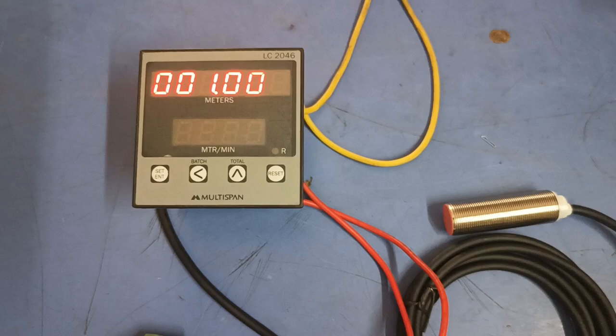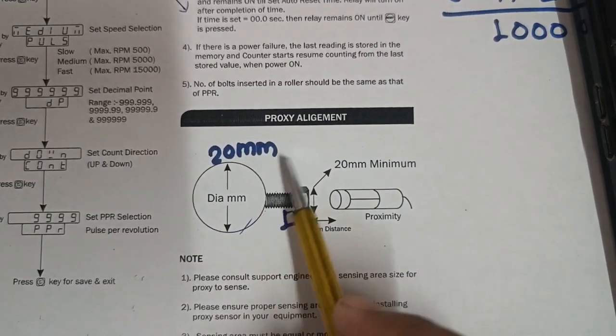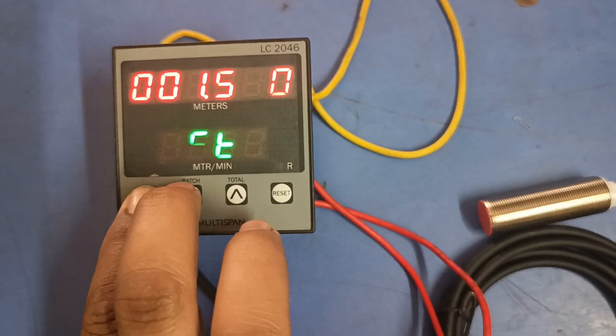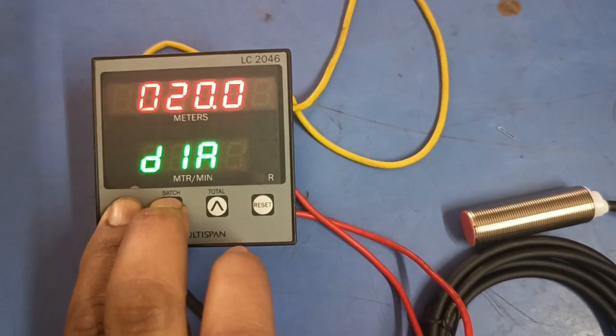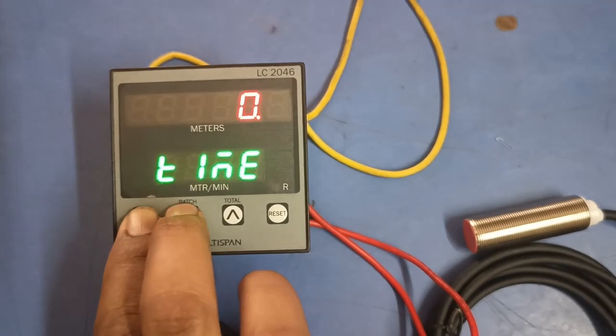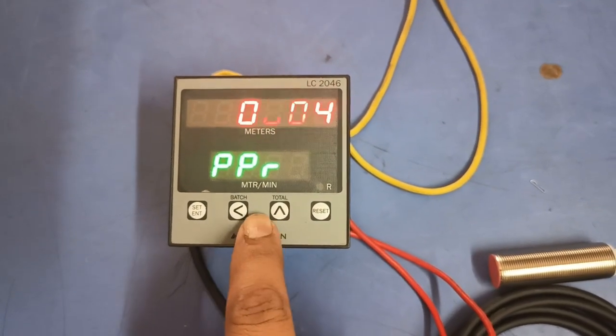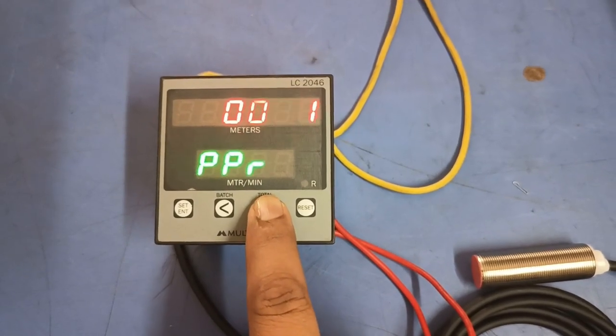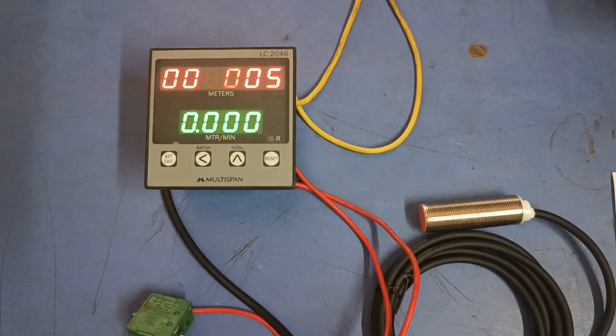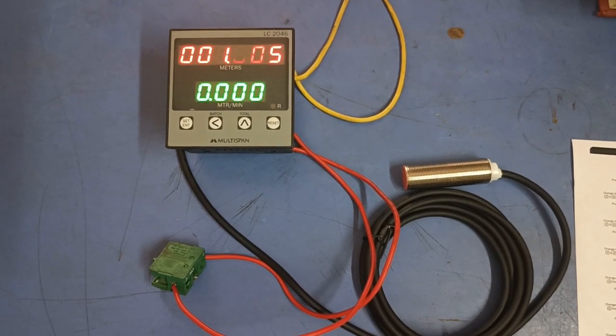The last parameter is PPR — pulse per revolution — how many times the sensor senses in one revolution. For accuracy, in some setups two or three bolts are connected so the sensor senses multiple times per revolution. Since we connected only one bolt, we set PPR to one. If you connect two or three bolts, set your PPR value accordingly. I hope you understand how to install the Multispan LC2046 length counter meter and do proper parameter settings. If you like this video, please press the like button.